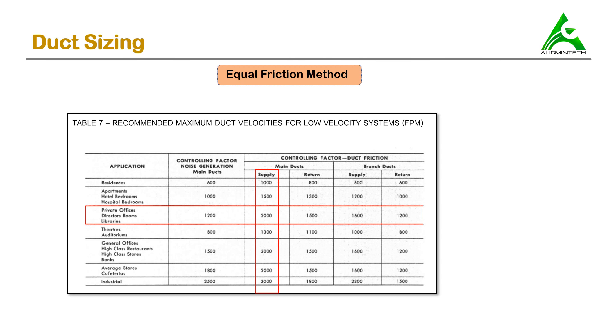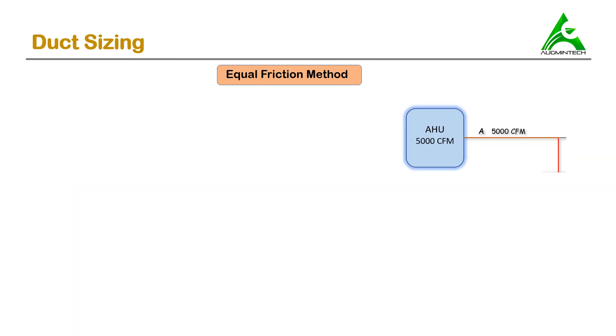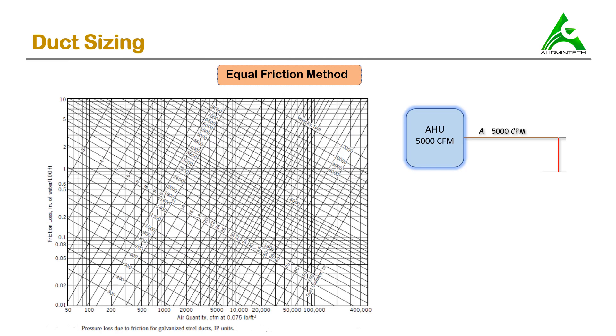Carrier suggests the maximum allowable velocity of flowing air in the duct is 2000 FPM. The next step is to determine the maximum velocity of air in our sample project. It's important to understand that the maximum velocity occurs in the first section, section A, because as air flows further, its velocity decreases. So we'll determine the velocity in section A as the maximum velocity for our project.